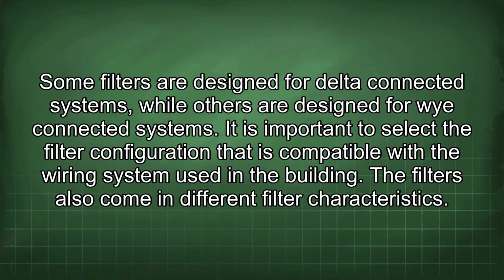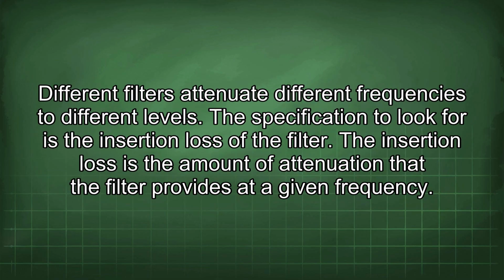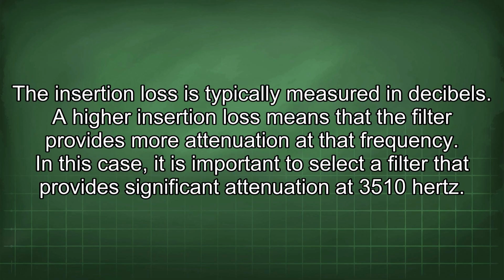The filters also come in different filter characteristics. Different filters attenuate different frequencies to different levels. The specification to look for is the insertion loss of the filter. The insertion loss is the amount of attenuation that the filter provides at a given frequency. The insertion loss is typically measured in decibels. A higher insertion loss means that a filter provides more attenuation at the frequency. In this case, it is important to select a filter that provides significant attenuation at 3510 Hz.